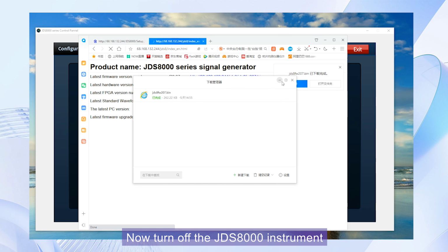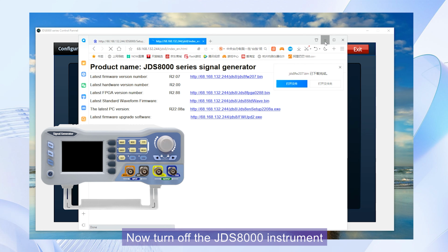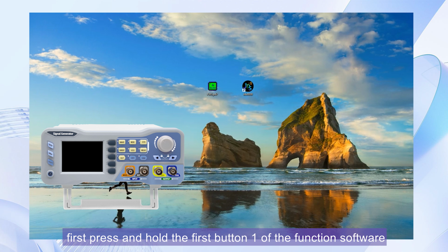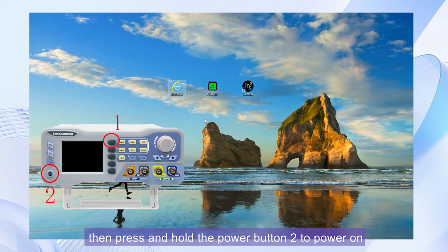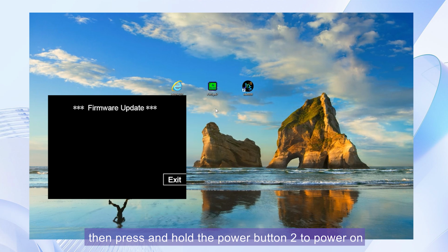Now turn off the JDS8000 instrument. First press and hold the first function button, then press and hold the power button to power on. This enters the firmware update interface.